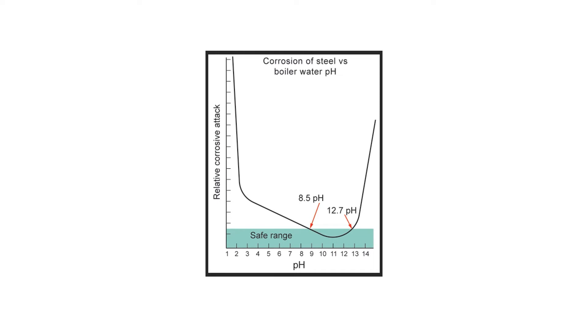Boiler water pH. Maintaining an acceptable boiler water pH is very important. Boiler water with a low pH is acidic and can be corrosive to metal exposed to the acidic water. Continuous operation of a boiler with acidic water will result in a loss of the passivating magnetite layer, which is unstable in acidic or slightly basic conditions. This loss can result in generalized corrosion of the metal throughout the boiler or more localized corrosion in specific areas.